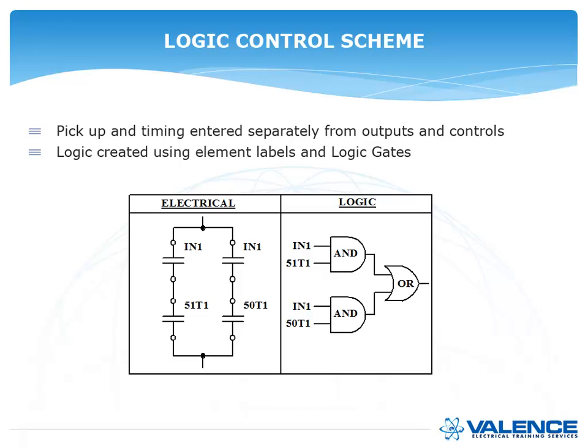This is the logic control scheme, so it looks like a typical logic diagram. So if you look at the electrical on the left, you have IN1 and 51T1, and those are two contacts in series, so that means an AND gate. So if you look at the logic diagram on the right, you have IN1 on the top and 51T1 underneath it, and they both go into an AND gate. And then we have IN1 and 50T1 in series, so that's another AND gate. Both of those contacts, or both sets of those contacts, are in parallel, so that's an OR gate. So that's how you translate from an electrical diagram into a logic diagram.